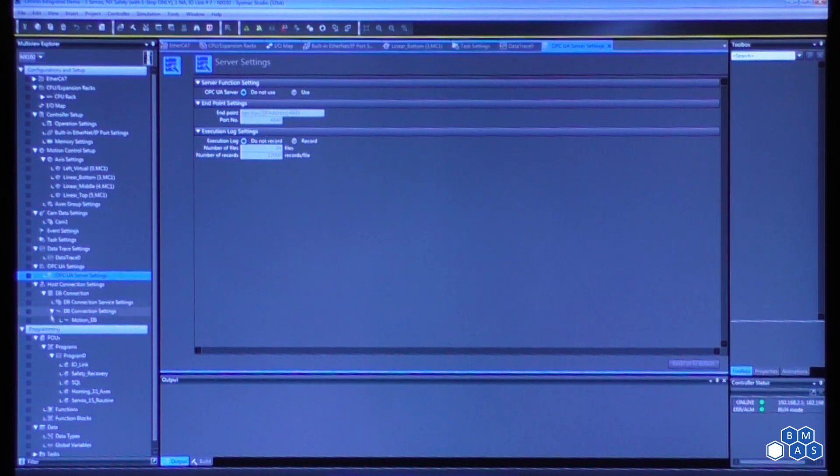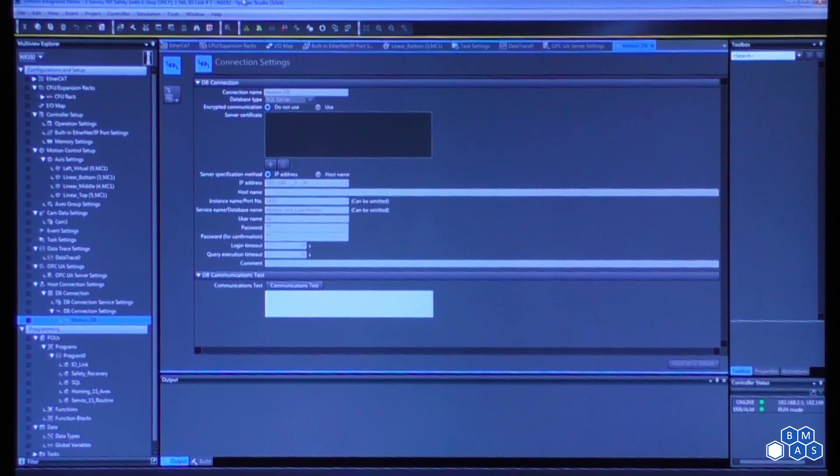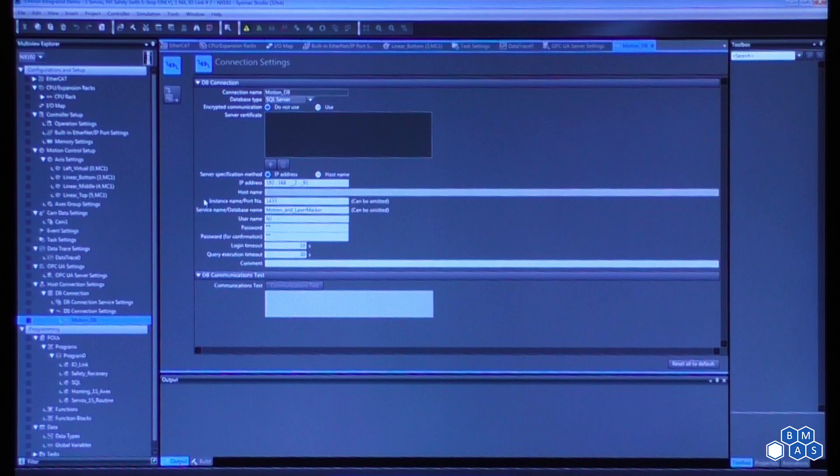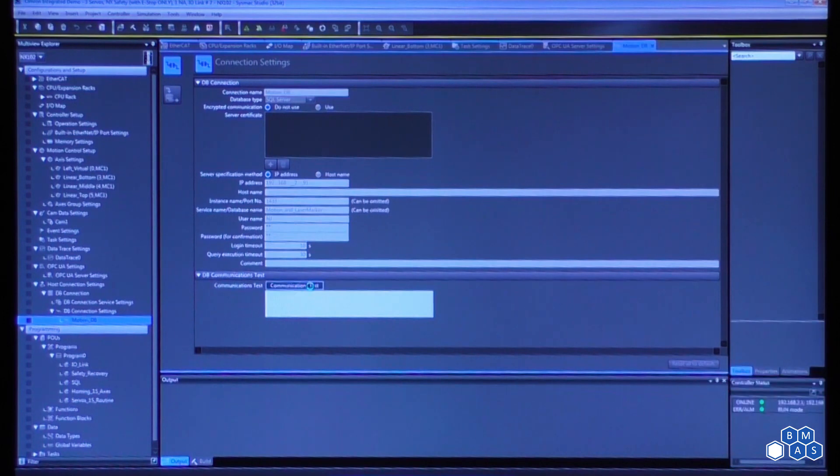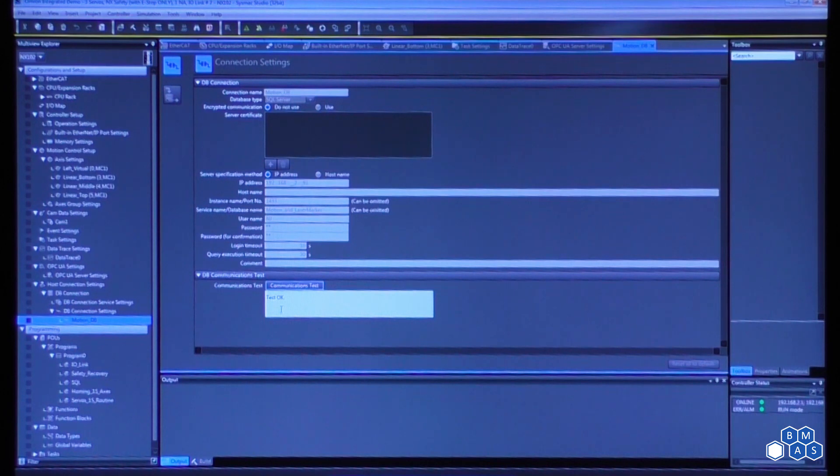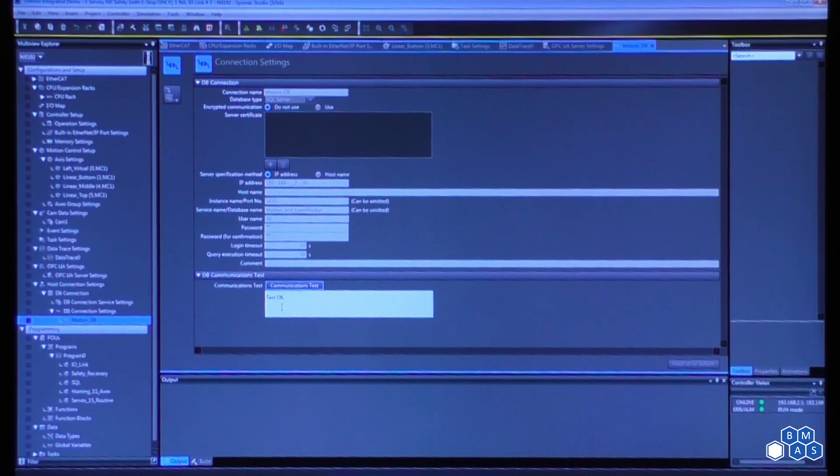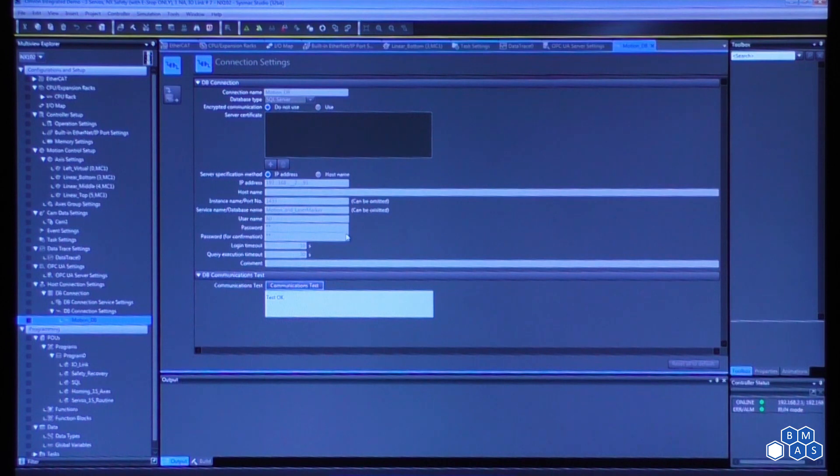This processor also supports databasing. So when we come into the databasing, what it's going to do is ask you what is the IP address or the host name that you're interfacing to, the port number, what is the database name, and then what's the login credentials for it. So once we establish all of that, go online with the processor, it'll come back and it'll ask us if we want to do a communication test, and if we have that database on that network on these connections, it'll come back and say test okay. So that is an instantaneous method for a lot of customers. If they want to test if they can access their database directly, this is something we can do in just a simple demo. We have done this in the past for some customers where we just connected it and it just worked, and we've had a lot of success with that.